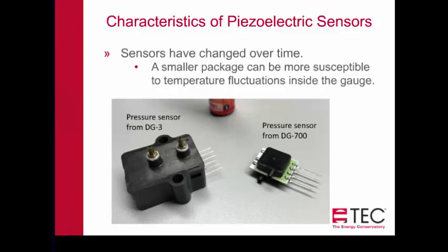Pressure measurement is very susceptible to changes in temperature. The smaller package, while more desirable for packaging, is now more susceptible to temperature fluctuations inside the gauge. The sensor on the left — from the DG3 — has much more mass, so any temperature effect takes longer to meaningfully affect the values. The smaller DG700 sensor has a much smaller body, so we have to consider what the internal temperature gains of the gauge are.